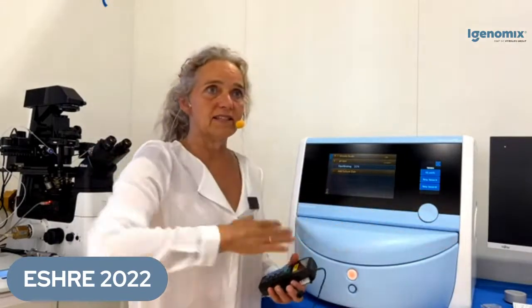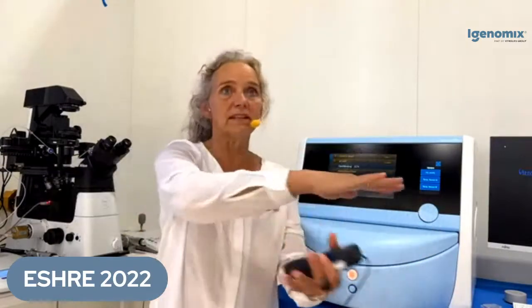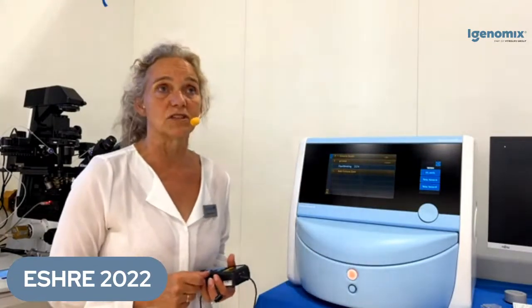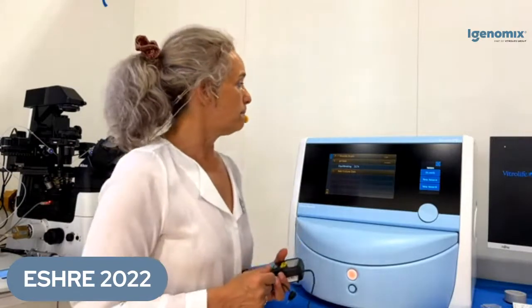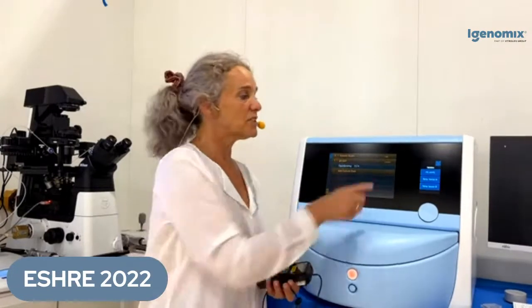The rotating plates that hold the dishes and move them to the camera have 2 independent working temperature sensors. If one of them should accidentally malfunction, the other one will take completely over the control, and there will be a warning on the screen that you should contact Vitrolife technical support, and they will come immediately according to the maintenance and service agreement that you have. But you can still culture your embryos inside because the other one is taking over. Still, you should validate and calibrate each of them individually.